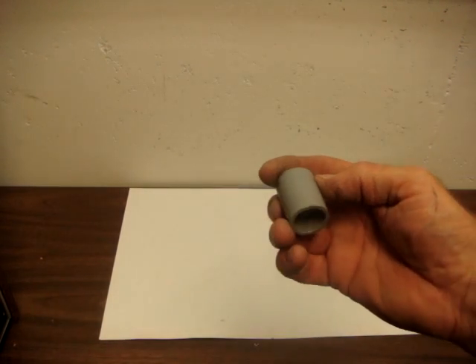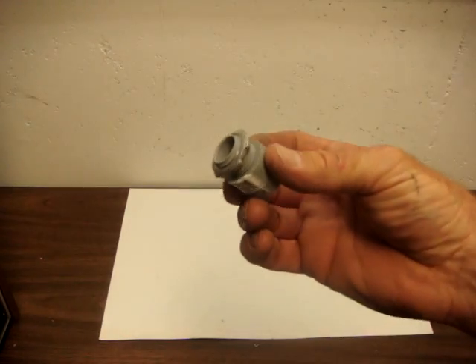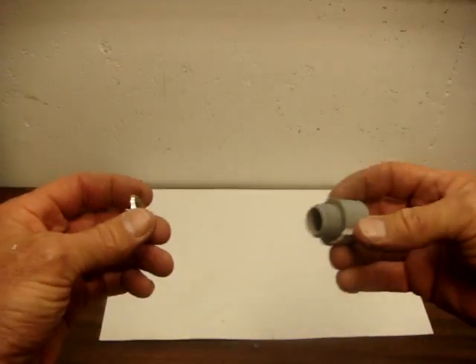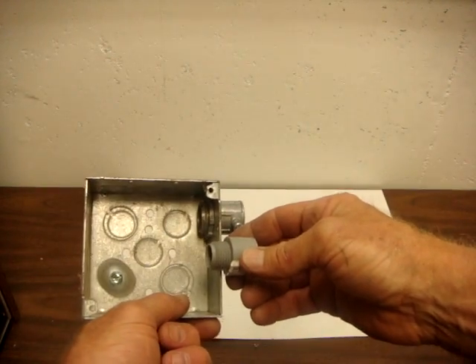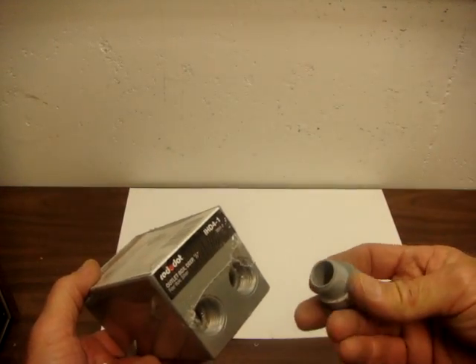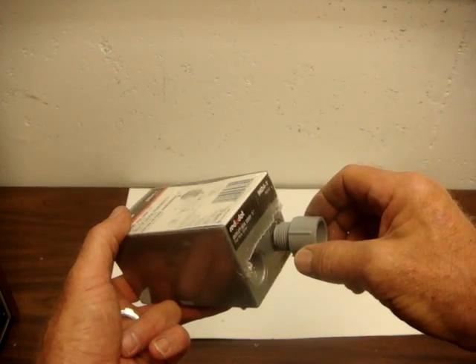The coupling is only one of the fittings that you can use with PVC conduit. There is also a male adapter. With the male adapter and a lock nut, you can use PVC conduit to go into metal boxes. That one would work on the interior or on an exterior application. You could use this to thread into the hub of the metal box and glue the PVC conduit to it.